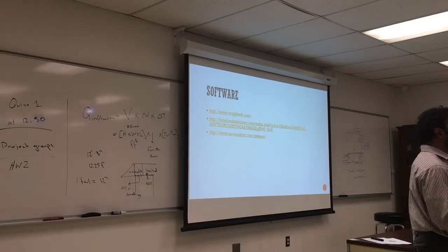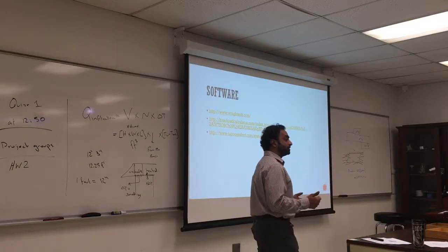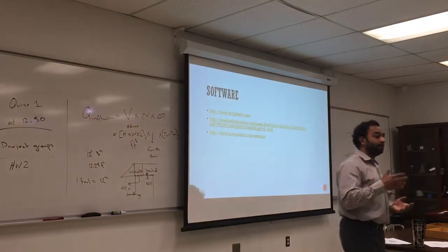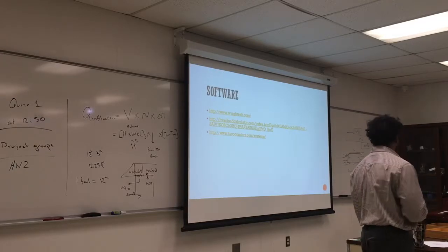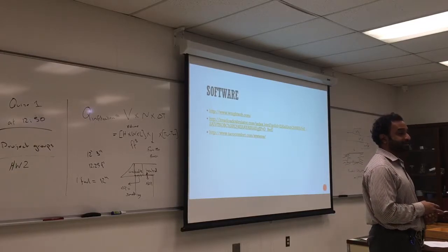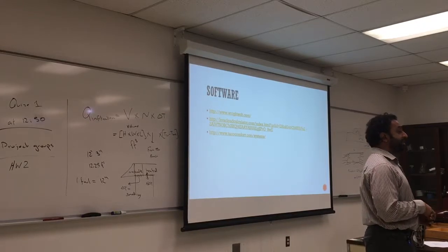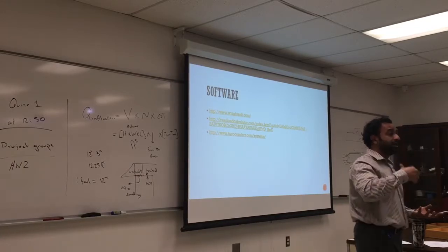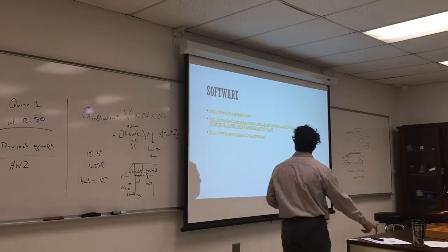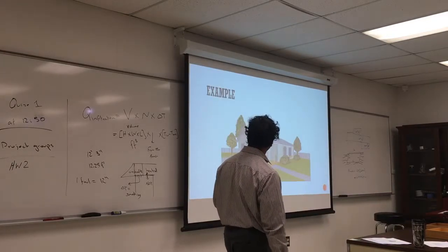But now you can do it by hand using the Excel sheet, so you know how you design the room, and you can change that back and forth. The issue with the software is that they have a limited database, and they assume all rooms are square, and if anything changes, the software cannot compensate for it. It's better to know what's going on behind the scenes and know how to calculate the heat loss and heat gain.